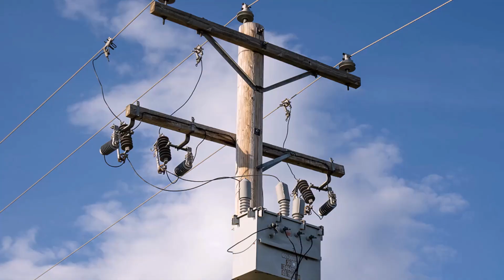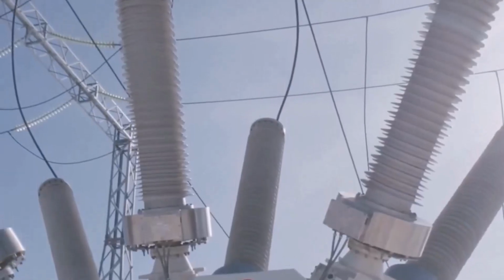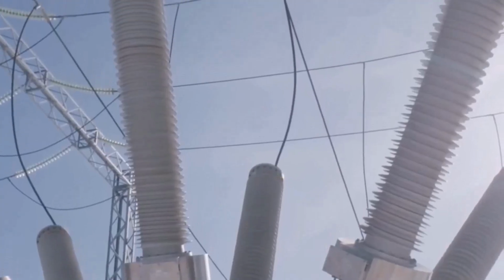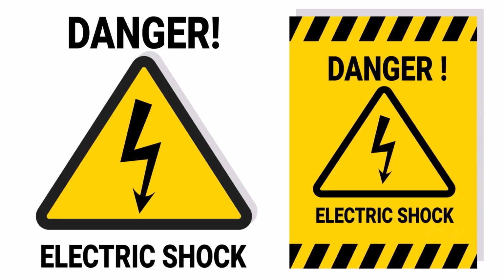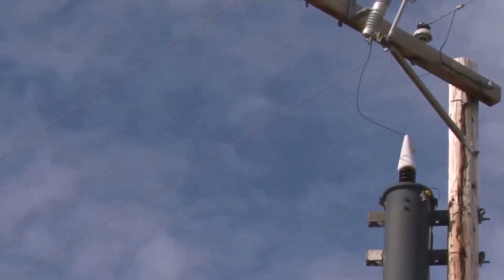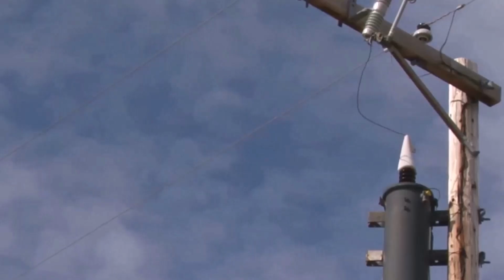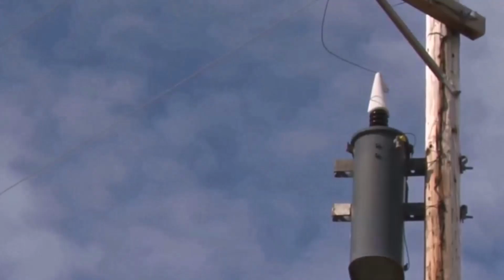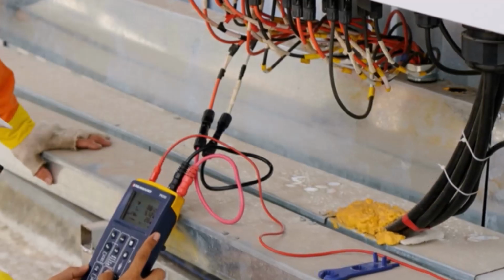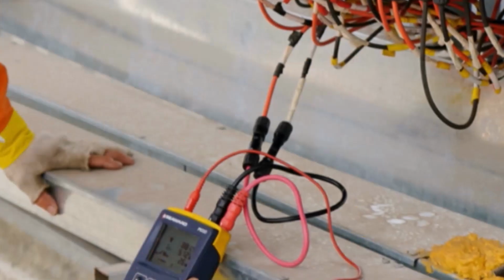It helps to stabilize the voltage and provides a safe path for fault currents to flow in case of a problem, like a short circuit. This can prevent dangerous electric shocks and protect equipment from damage. This ability to create a solidly grounded neutral is one of the primary reasons why Y connections are so widely used in distribution networks that supply power directly to consumers. Safety always comes first, and a grounded Y helps ensure it.